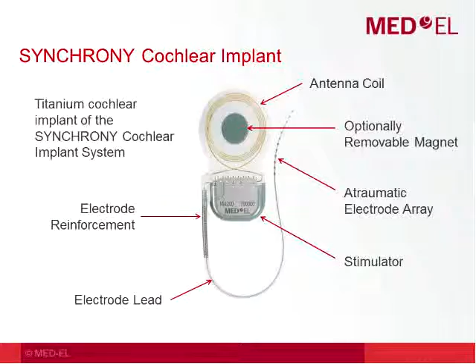Then there's also a long part to the electrode array that leads to the inner ear, and that can actually be some extra length that is coiled up so that children and adults don't need a different size cochlear implant. The same implant is used for everyone. And then our electrode array is also reinforced for extra strength to protect all of those delicate wires inside the electrode array.